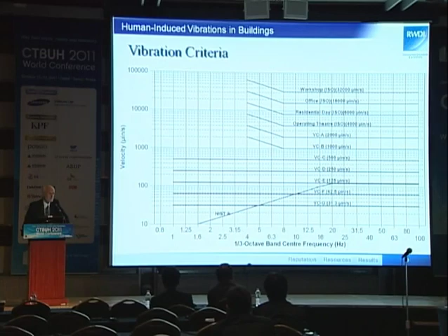The other curves below that are all other vibration criteria primarily intended for very sensitive equipment. The bottom 2 to 3 curves are actually very difficult to achieve, but you do find some manufacturers requiring those kinds of levels, which can cause issues when you're trying to design to them. It's often necessary to contact the manufacturer and ask, are you really serious about these? In many cases they will have one of their own experts look at it, and often the answer is yes, actually, we don't have to be dead on. As long as you're close, that's good enough.